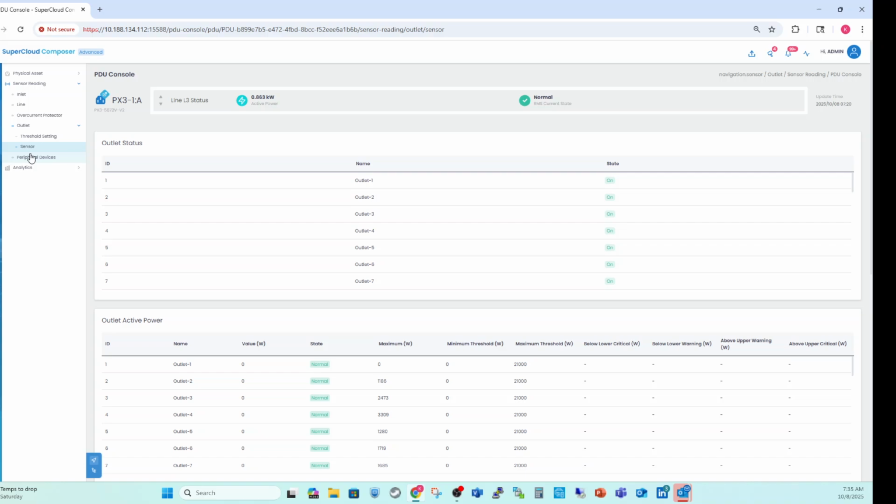So we see some movement here within the PDU manufacturers and other manufacturers starting to move to Redfish, and that's very important because then we build in standards for PDU management, and it certainly makes Supermicro's job and our developer team's job much easier because now we're pulling in the entire metadata from one particular API get call as opposed to having to walk the information.